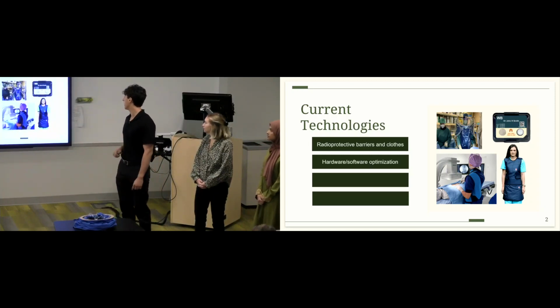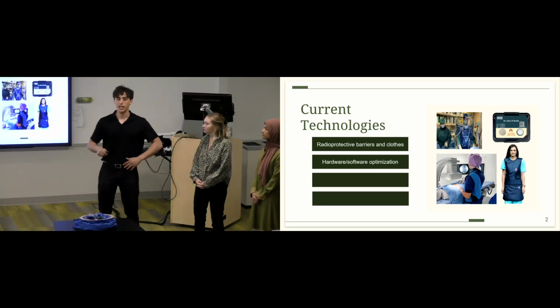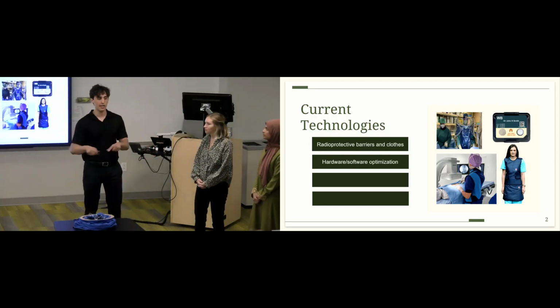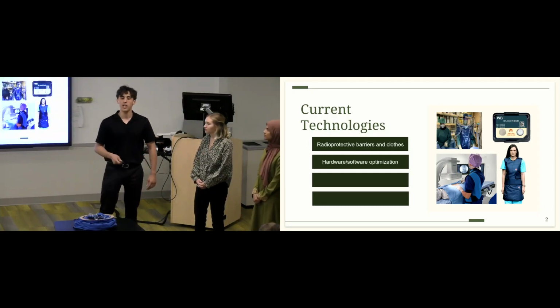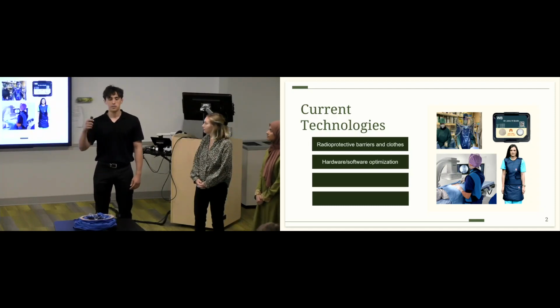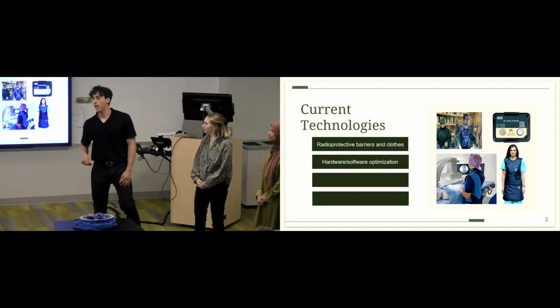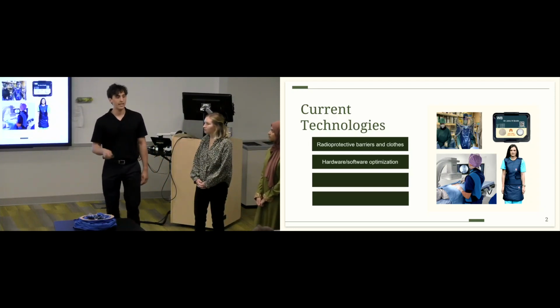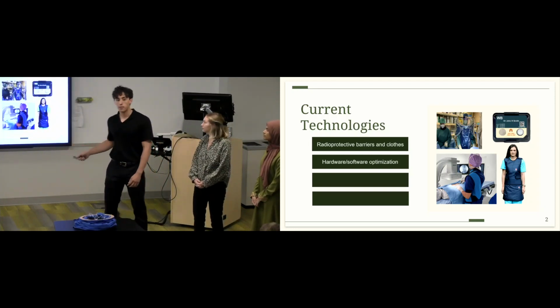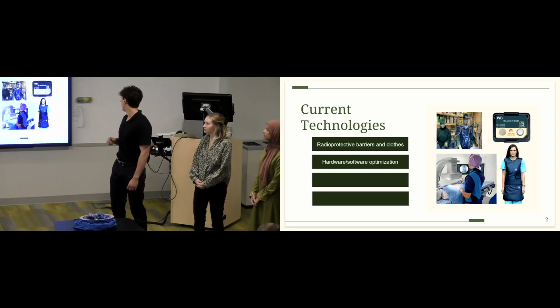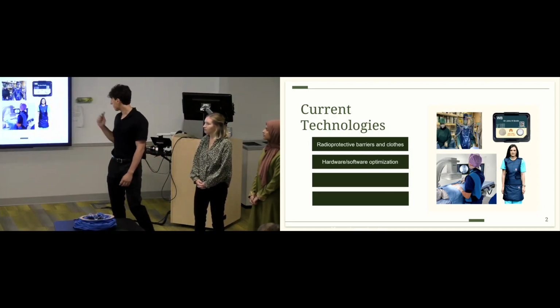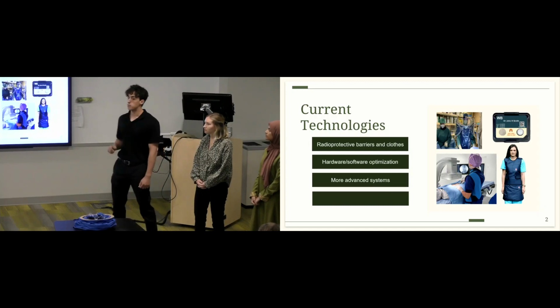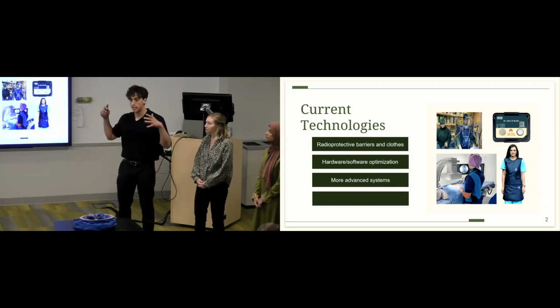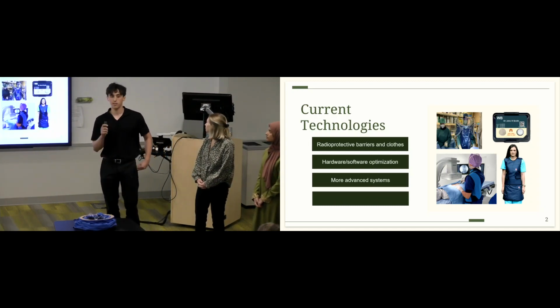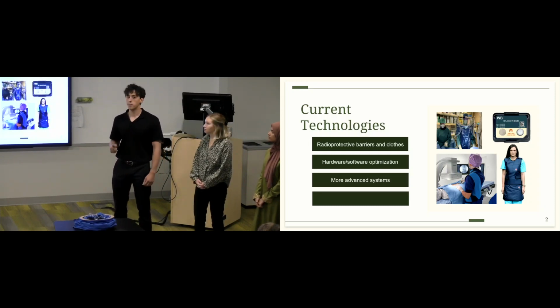Two, hardware and software optimization. The physician during these procedures is looking at a big screen which has a frame rate since it's a live image. These frames can range from 15 to 10 to 4 to 2 to 1 frame a second that directly correlates with how much radiation is being emitted from the machine. This is optimized by the physician without compromising patient success, procedure success. More advanced systems do exist, like the more advanced suits that are being used, but they are very heavy and very expensive, being inaccessible to most hospitals.